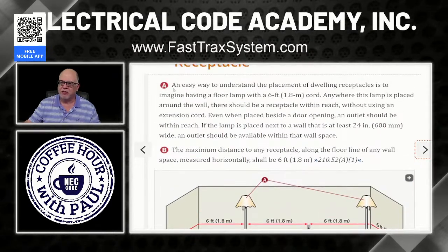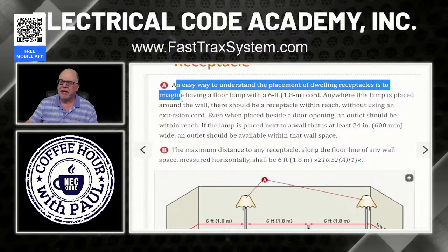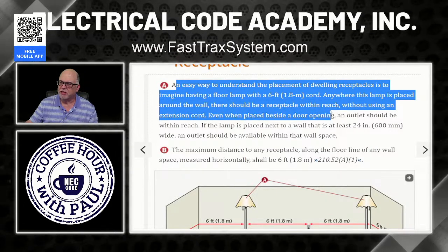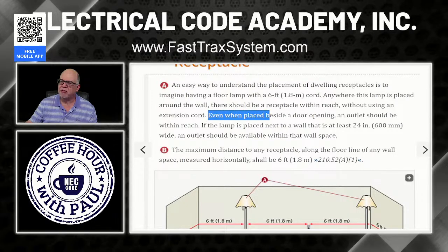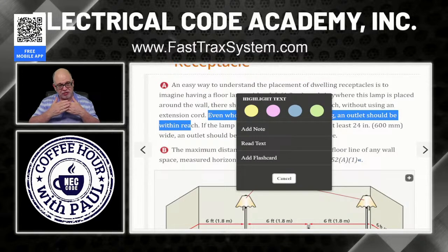So here you go. It says, an easy way to understand the placement of dwelling receptacles is to imagine having a floor lamp with a 6 foot cord. Anywhere this lamp is placed around the wall, there should be a receptacle within reach without using an extension cord. That's what we're trying to achieve. Even when placed beside a door opening, the outlet should be within reach, because there's supposed to be one within 6 feet of a break in the wall line.